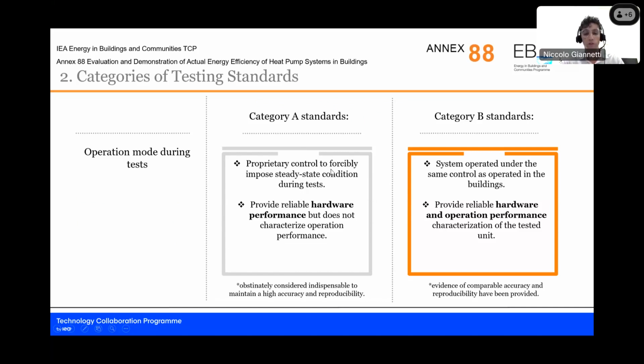So the actual control, the native control of the system, is deactivated, and a special control is included to obtain this special condition. When tested in this condition, these testing methodologies can provide values that are representative of maybe the equipment performance or hardware performance. But as the control system has been deactivated during this test, the results are not able to characterize the performance that is encountered in an actual building.